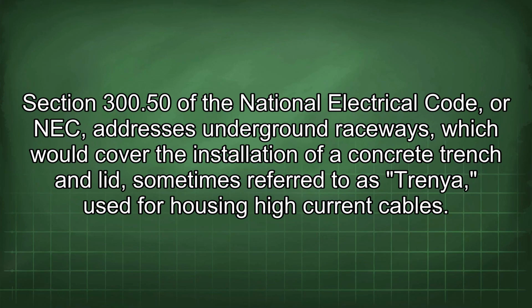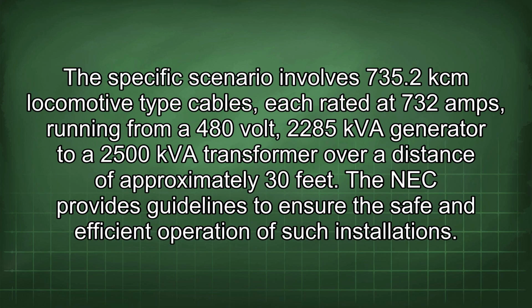Section 300.50 of the National Electrical Code, or NEC, addresses underground raceways, which would cover the installation of a concrete trench and lid, sometimes referred to as Trenya, used for housing high-current cables. This specific scenario involves 735.2 kcm locomotive type cables, each rated at 732 amps, running from a 480-volt 2285 kVA generator to a 2500 kVA transformer over a distance of approximately 30 feet. The NEC provides guidelines to ensure the safe and efficient operation of such installations.